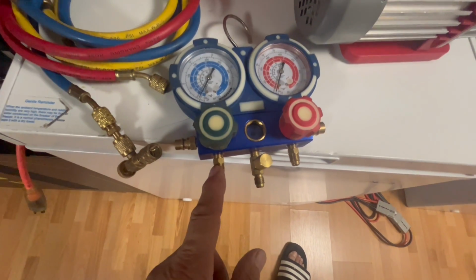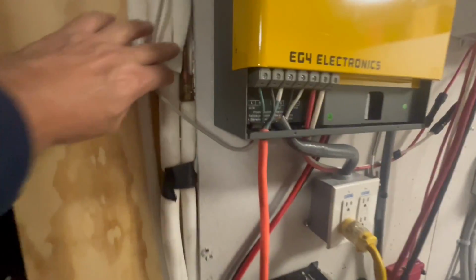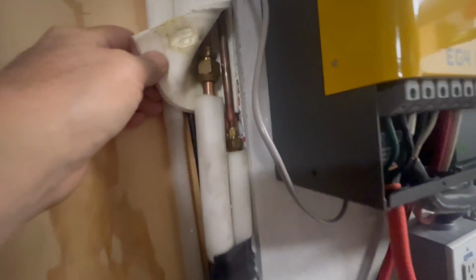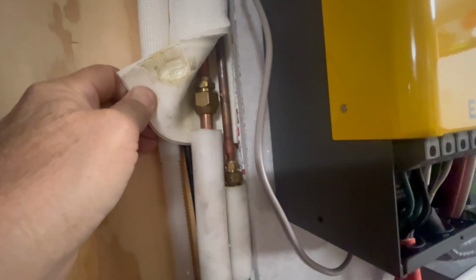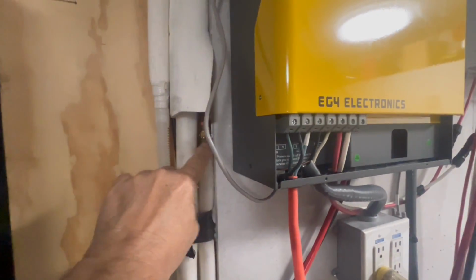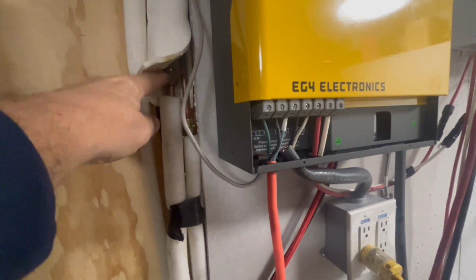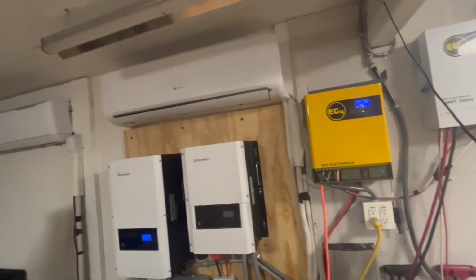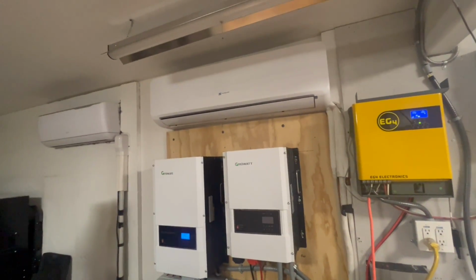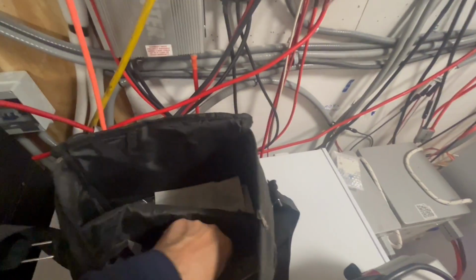When I was connecting the line set right here to the head unit, there's a high side and low side - low side's the big line, high side's the little line. I put the Nylog Blue on the threads here before I put it together, and it's been around 4 years, and I've had no leaks with anything yet. So it really works good. The Nylog Blue is important because you always have vibration from the compressor and the fan running.